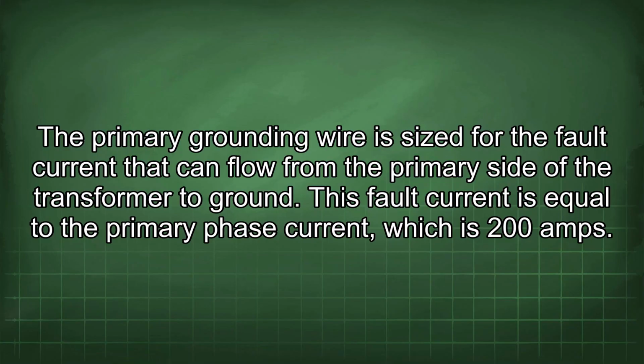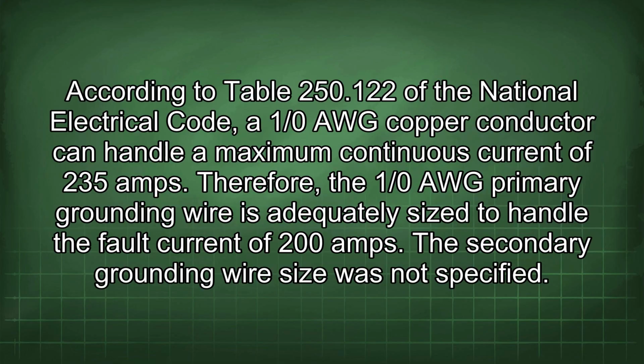The primary grounding wire is sized for the fault current that can flow from the primary side of the transformer to ground. This fault current is equal to the primary phase current, which is 200 amps. According to Table 250.122 of the National Electrical Code, a 1/0 AWG copper conductor can handle a maximum continuous current of 235 amps. Therefore, the 1/0 AWG primary grounding wire is adequately sized to handle the fault current of 200 amps.